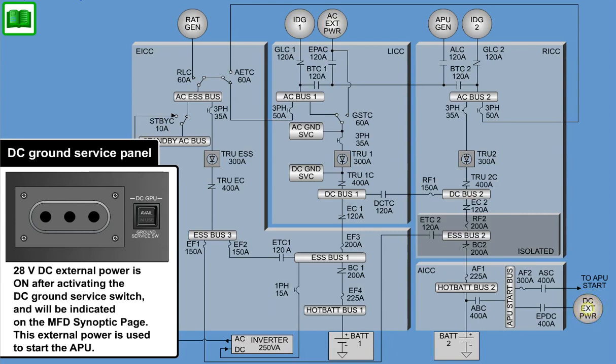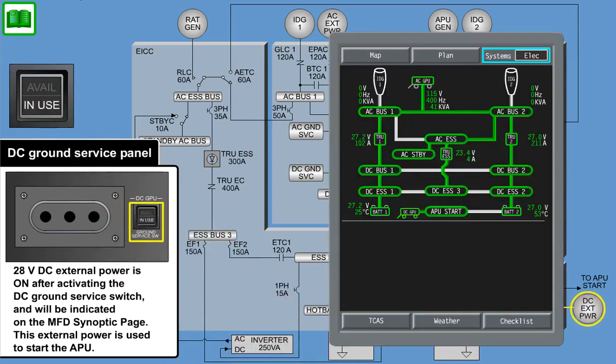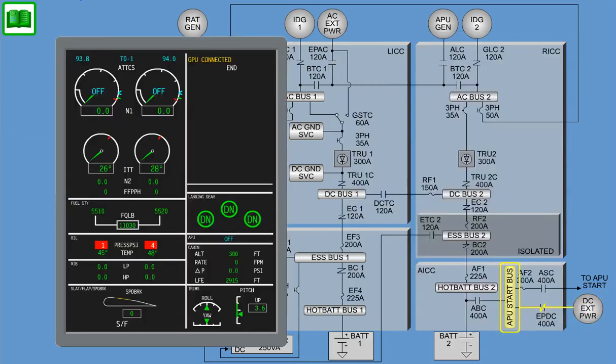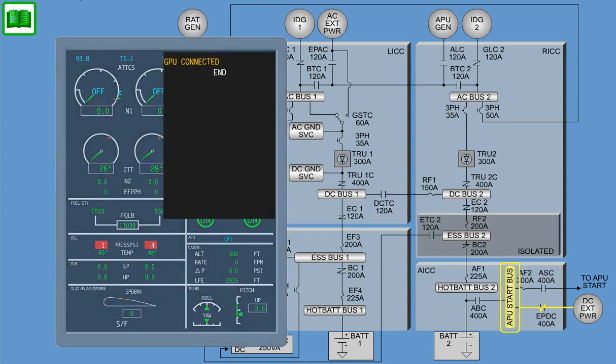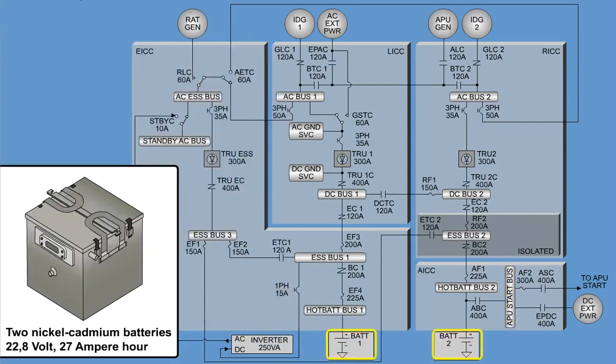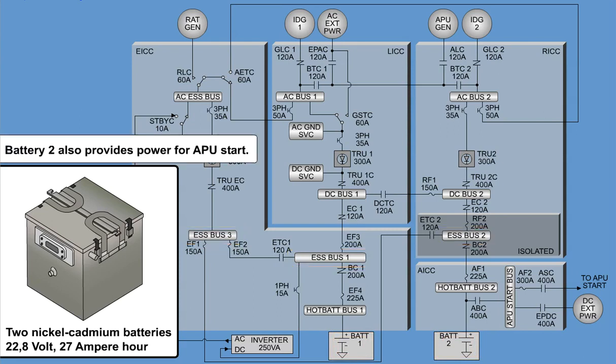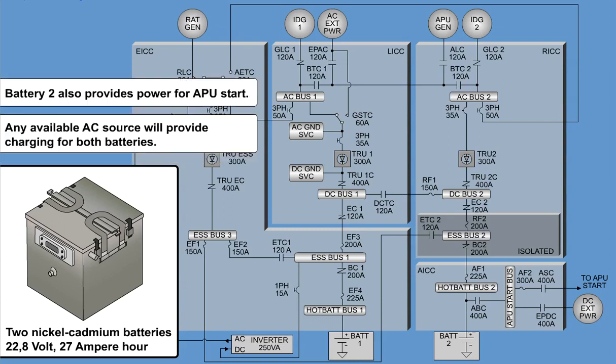28-volt DC external power is on after activating the DC ground service switch, and will be indicated on the MFD synoptic page. This external power is used to start the APU. In case of releasing the parking brake with an external power AC or DC connected to the airplane, the caution message GPU connected will be shown on the EICAS. Two nickel-cadmium batteries, rated at 22.8 volt, 27 ampere hour, provide the essential loads in case of power failure of all generators. Battery 2 also provides power for APU start. Any available AC source will provide charging for both batteries.